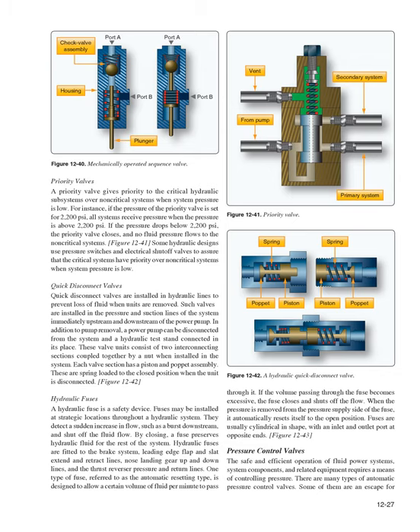One type of fuse, referred to as the automatic resetting type, is designed to allow a certain volume of fluid per minute to pass. If the flow becomes excessive, the fuse closes and shuts off the flow. When the pressure is removed from the pressure supply side of the fuse, it automatically resets itself to the open position. Fuses are usually cylindrical in shape, with an inlet and outlet port at opposite ends.